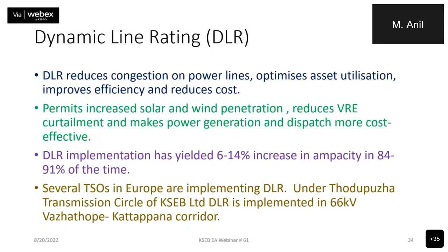Then the next innovation, strategic innovation, dynamic line rating. So dynamic line rating reduces congestion on power lines, optimizes asset utilization, improves efficiency, and reduces cost. It permits increased solar and wind penetration, reduces VRE curtailment, and makes power generation and dispatch more cost-effective. DLR implementation has yielded a 6 to 14% increase in ampacity in 84 to 91% of the time. Several transmission system operators in Europe are implementing DLR. Under our transmission circle Todupuzha of KSEB Limited, DLR is implemented in the 66kV Vazhathope-Kattappana corridor.